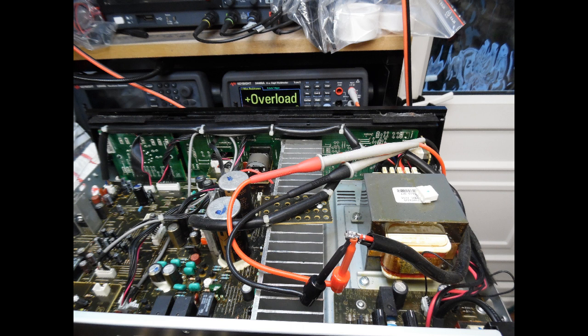What you can see here is I've used some hook clips, and without touching the probe leads, I'm measuring the transformer primary winding resistance. As you can see on this multimeter, it's indicating overload, which tells me it's open circuit.